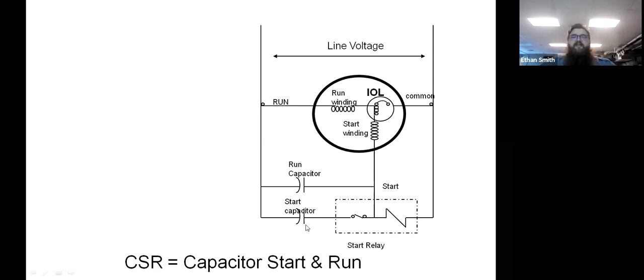Because they're only meant to be in circuit for a couple seconds, but they give you that extra kick to get that motor spinning. Once it's spinning, generating back EMF, it opens up that relay and drops that start capacitor out. A lot of guys get really intimidated by potential relays because they don't know what's going on in them. But guys, it's just a relay in parallel with the start winding with a normally closed contact. That's all it is. Any questions about that, guys?